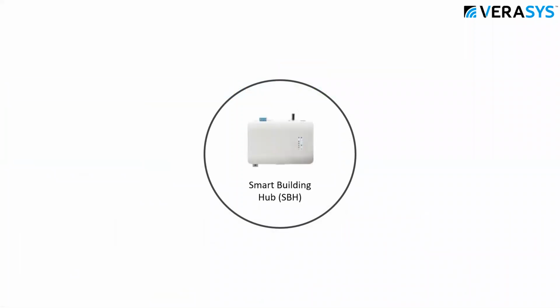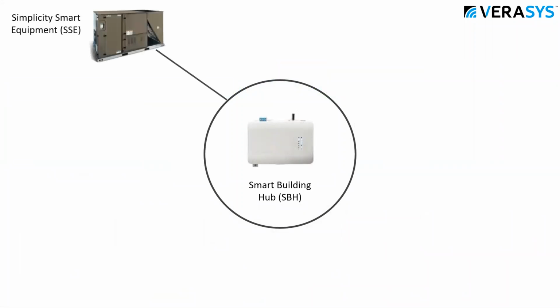Here I'm going to describe the ecosystem that works with Verasys, sometimes referred to as Simplicity Smart Equipment. The equipment that can be on the BACnet MSTP network for the Smart Building Hub is limited to about 100 devices. But if you think about it, 100 rooftop units is a pretty large building.